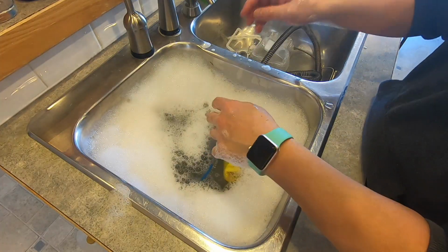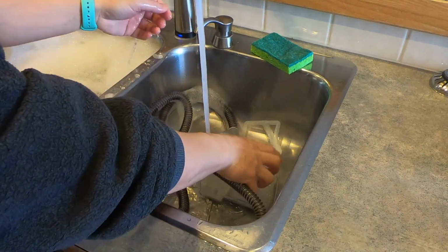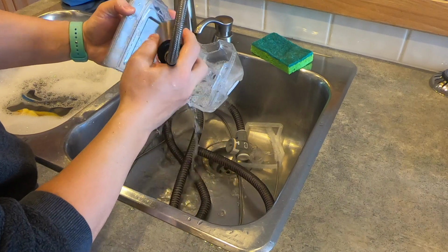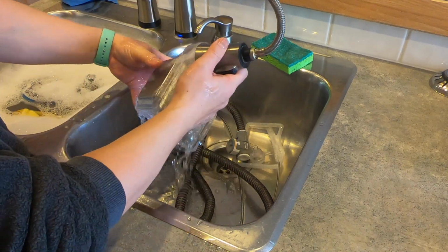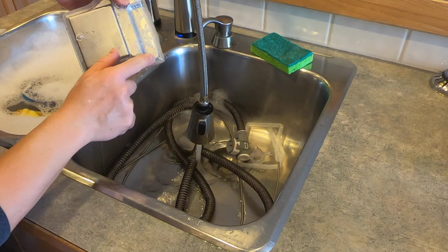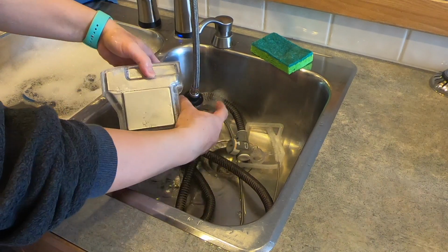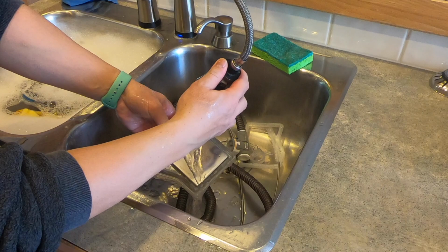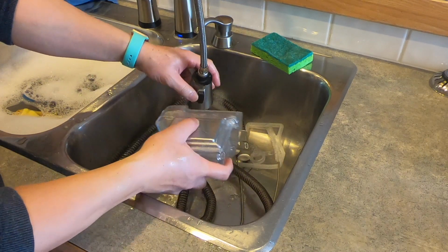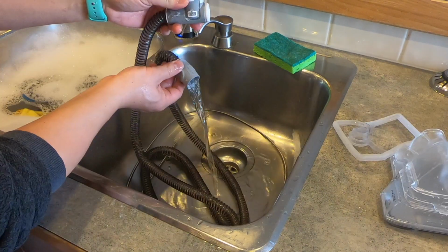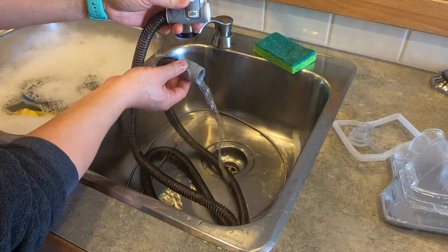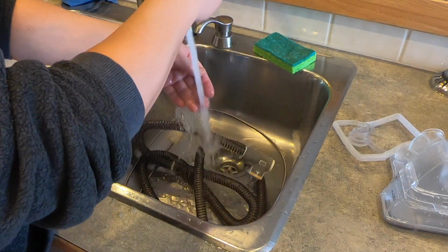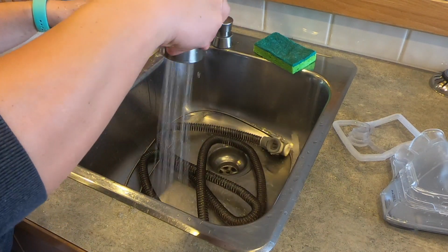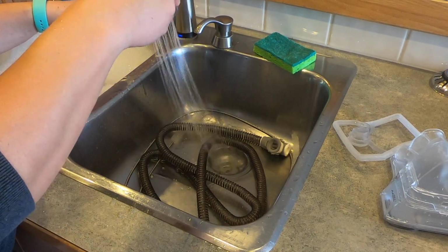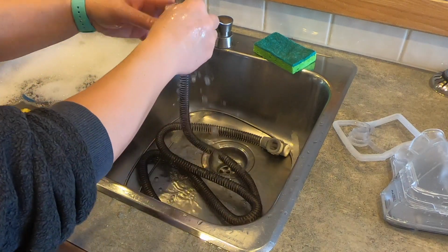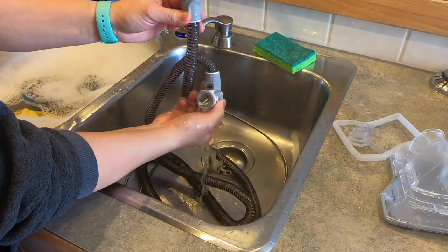So we're going to let that soak for a little bit. We can rinse our parts. Now this is that little hole I was telling you about earlier, right here. You want to put some clean water through that, and then swish it around and dump it out. And finally, I like to rinse the outside of the hose and my cleaning brush and everything with water just to get all the soap off of it. And then one more final rinse just to make sure there's absolutely no soap in there at all.